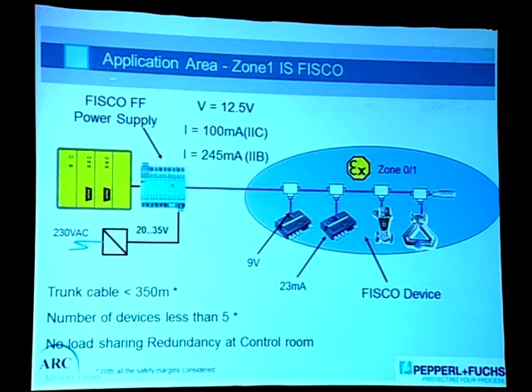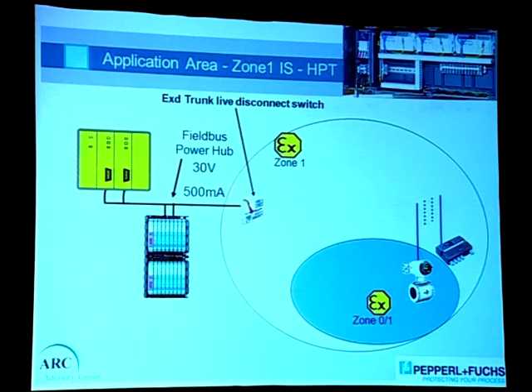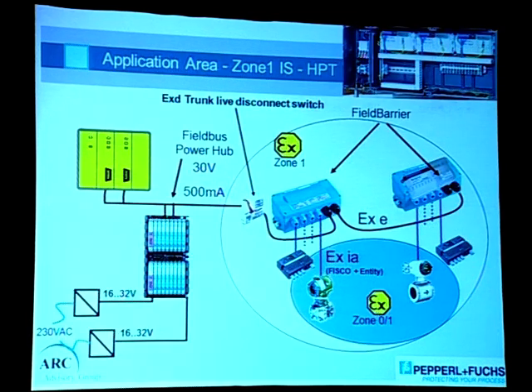Then we moved to FISCO, the Fieldbus intrinsic safe concept. We improved the voltage to some extent, not to a great extent, but we also classified the application regarding gas groups, IIC and IIB, and put in different current characteristics. But even though the current is sufficient to drive a certain number of devices, the voltage is the biggest problem. And again, with the traditional limitation of intrinsic safety, redundancy is absolutely not possible. So though it gives a certain improvement, it is not practically used in almost every plant because of some practical limitations. Then we moved into a different type of intrinsic safety.